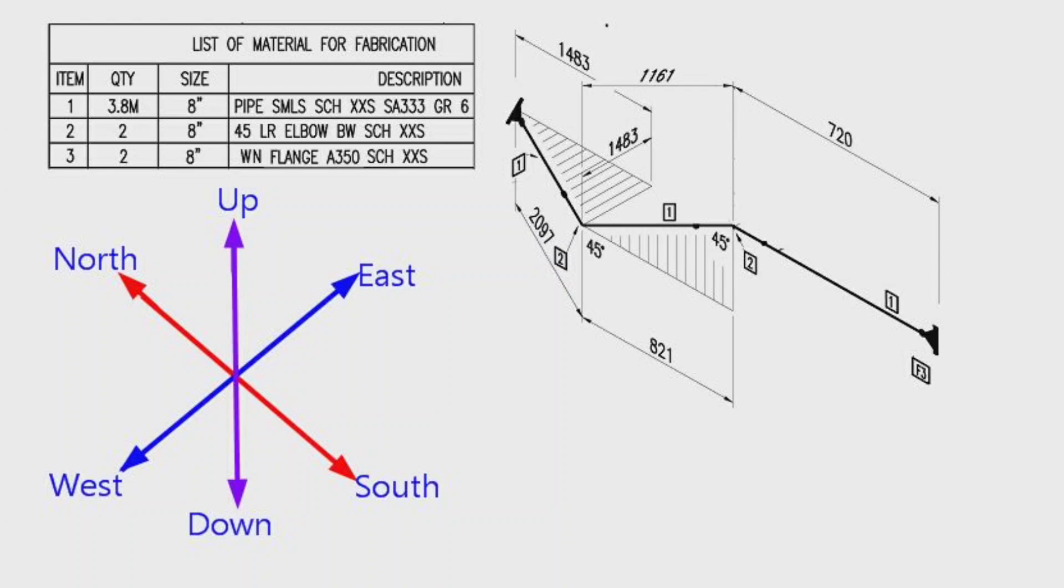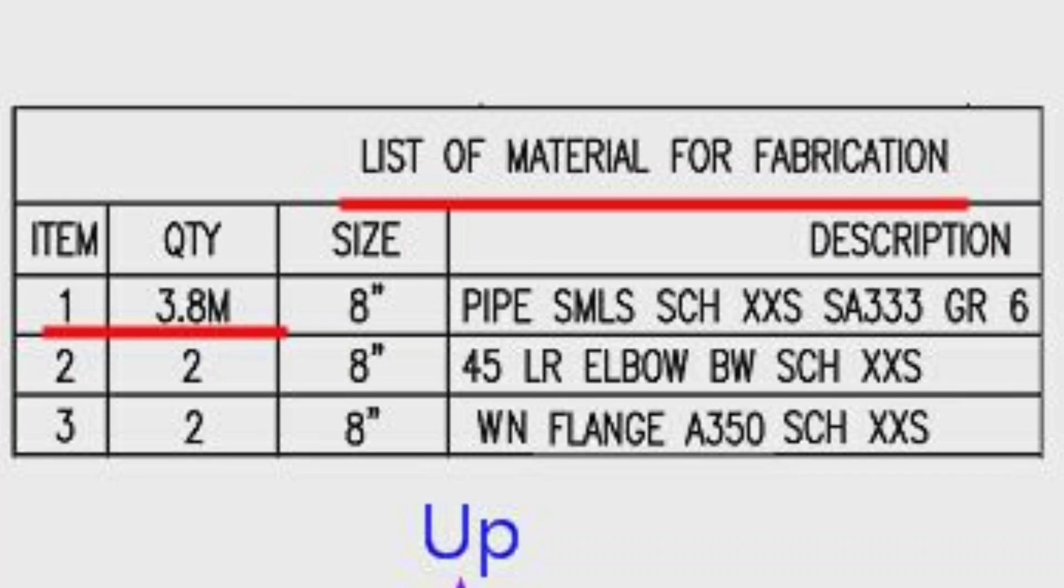Let's learn the materials which used in the pipeline. This is the list of materials for fabrication. Detail number 1 shows pipe, was used in several places in the pipe drawing. Let's look at the material list. The detail number 1: 3.8 meters length, 8 inches pipe, seamless, schedule is XXS, SA333 grade 6.